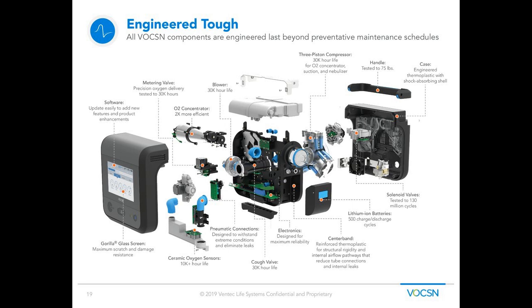The single piston banging back and forth in your portable suction pump today is not what's driving suction in VOCSN. It's actually a highly over-engineered three-piston compressor that gives you a much more consistent flow, runs at a much slower speed, and generates less heat and less wear and tear.